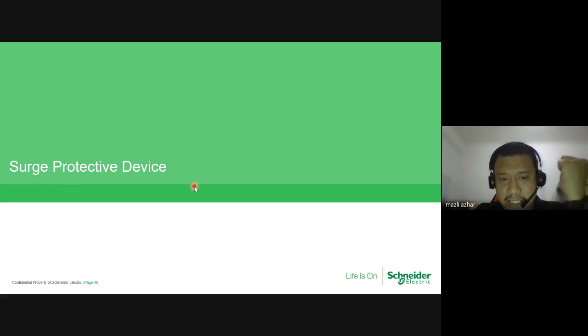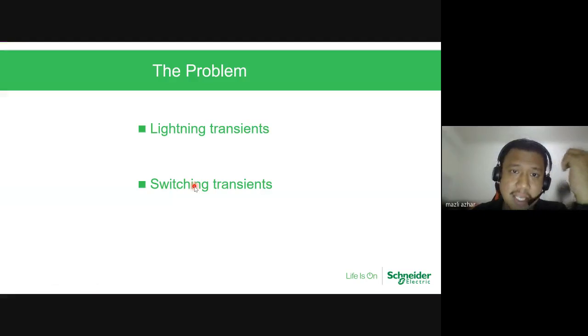So a bit of recap. MCB is to protect against overload and short circuit. RCCB is to protect against electrocution, or in simple layman's terms, leakage protection. Another one added is the surge protective device. The problem that we are facing now in Malaysia is two problems: lightning transient and switching transient. Transient from lightning means a lightning strike. Switching is based on the motor.